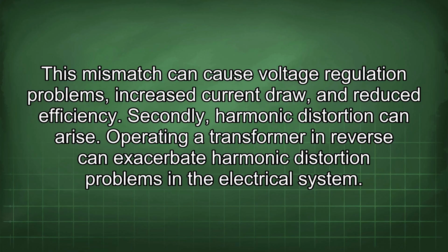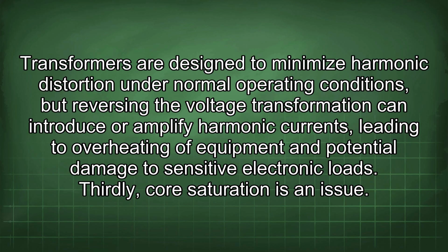Secondly, harmonic distortion can arise. Operating a transformer in reverse can exacerbate harmonic distortion problems in the electrical system. Transformers are designed to minimize harmonic distortion under normal operating conditions, but reversing the voltage transformation can introduce or amplify harmonic currents, leading to overheating of equipment and potential damage to sensitive electronic loads.